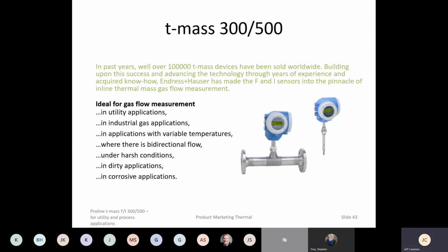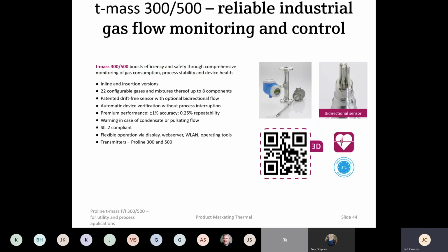Third technology that we're making a new introduction. This one actually was introduced next month, but we're already talking about it because it's pretty far down the line. Thermal mass meters. Endress+Hauser has been manufacturing thermal mass for many years now, over 100,000 in the field. So they're typically used in clean gas applications, a lot of utility applications, variable temperatures, bidirectional flow, that type of thing. So we've made some improvements to our current, and we've moved to the 300, 500 transmitter series. So we offer inline insertion versions. There's 22 now configurable gases in what's called the gas engine, and that's typically all the gases that are stored in the meter. We've introduced a new sensor, a new patented drift-free sensor.